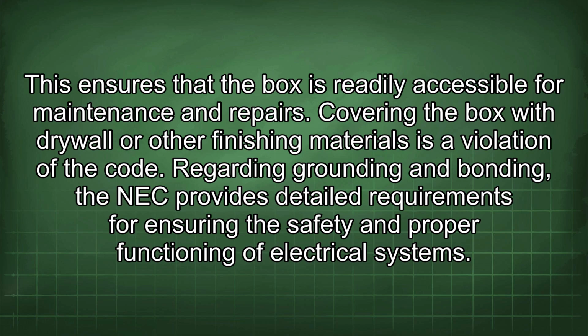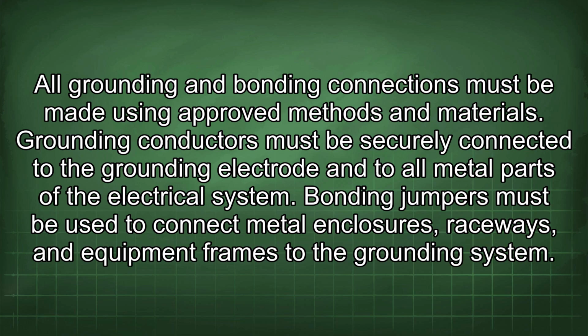Regarding grounding and bonding, the NEC provides detailed requirements for ensuring the safety and proper functioning of electrical systems. All grounding and bonding connections must be made using approved methods and materials. Grounding conductors must be securely connected to the grounding electrode and to all metal parts of the electrical system. Bonding jumpers must be used to connect metal enclosures, raceways, and equipment frames to the grounding system.